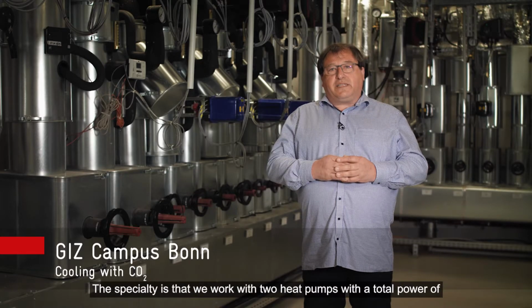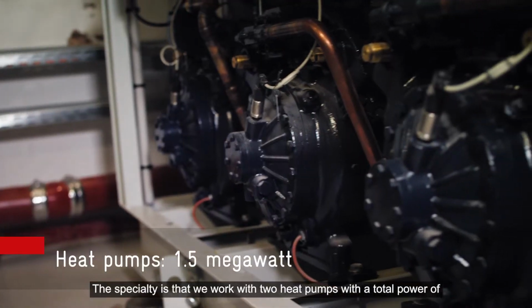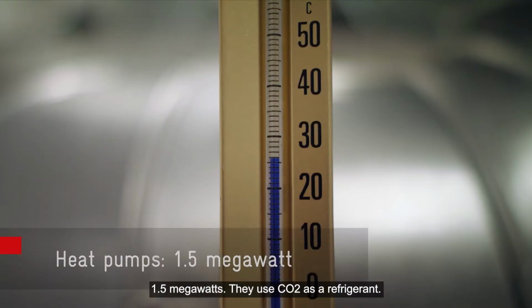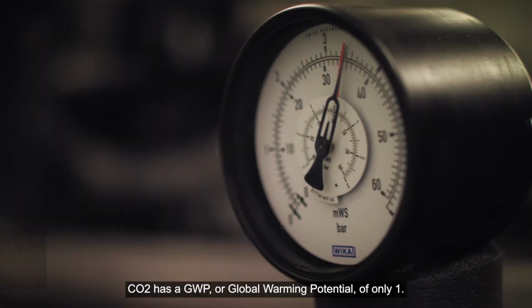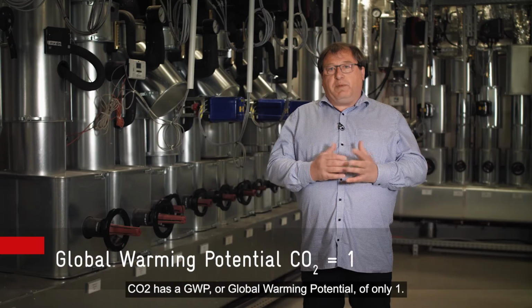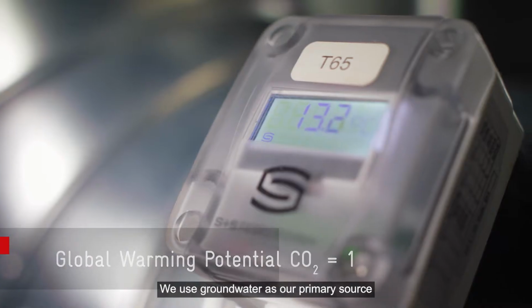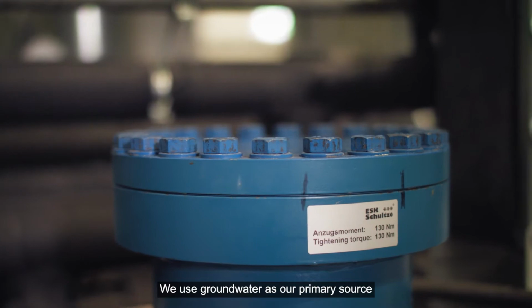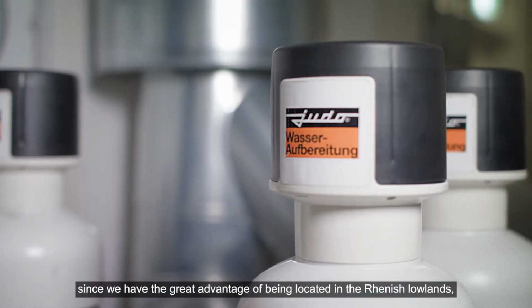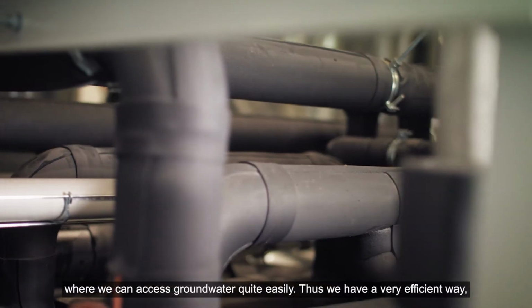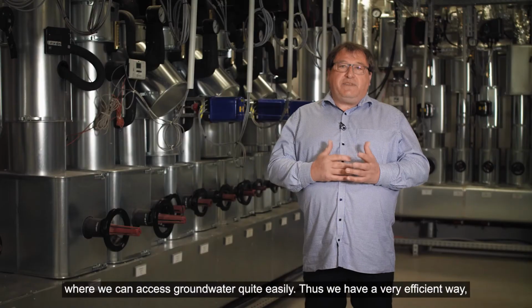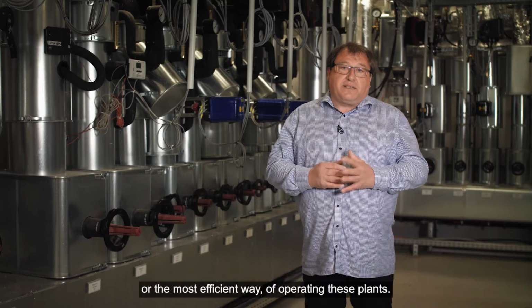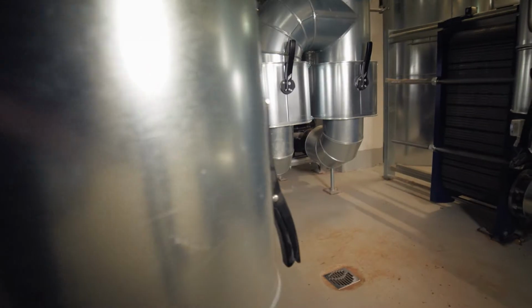The specialty is that we work with 2 heat pumps with a total power of 1.5 megawatts. They use CO2 as a refrigerant. CO2 has a GWP, or global warming potential, of only 1. We use groundwater as our primary source since we have the great advantage of being located in the Rhenish lowlands, where we can access groundwater quite easily. Thus, we have a very efficient way, or the most efficient way, of operating these plants.